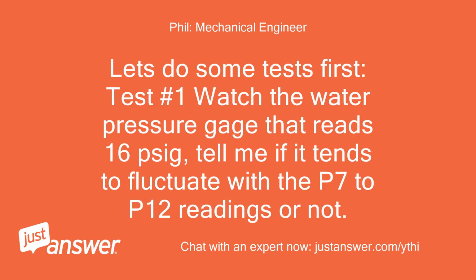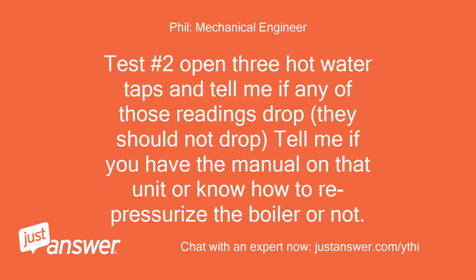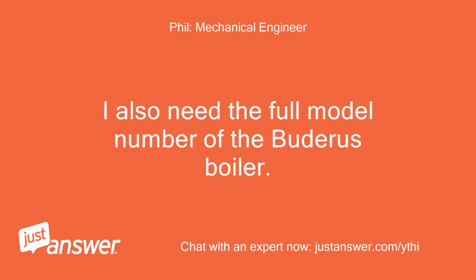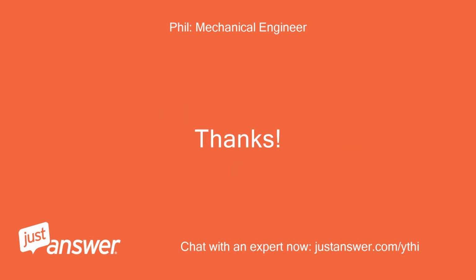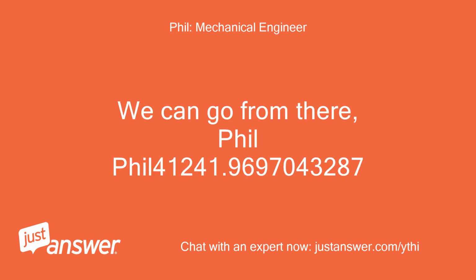Let's do some tests first. Test number 1. Watch the water pressure gauge that reads 16 psig. Tell me if it tends to fluctuate with the P7 to P12 readings or not. Test number 2. Open 3 hot water taps and tell me if any of those readings drop. They should not drop. Tell me if you have the manual on that unit or know how to re-pressurize the boiler or not. I also need the full model number of the Buderus boiler. We can go from there.